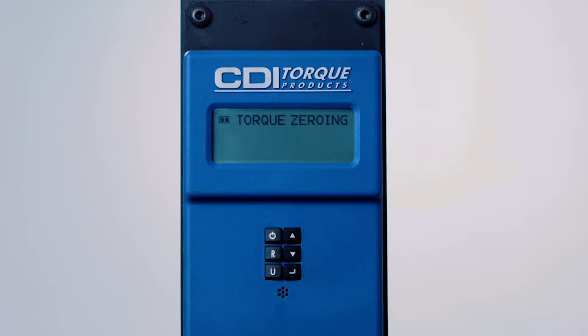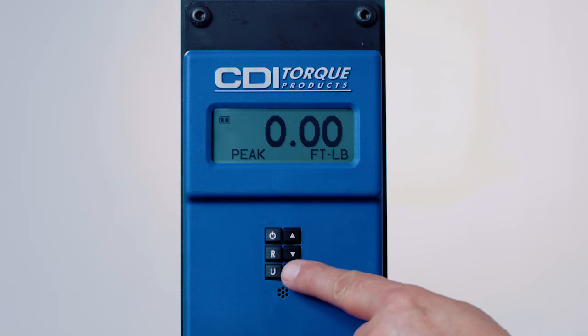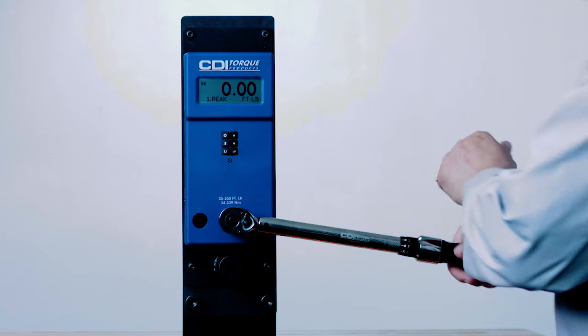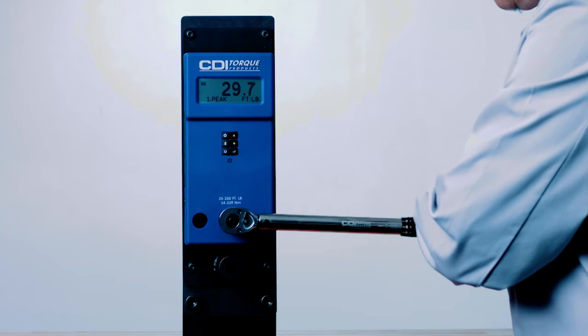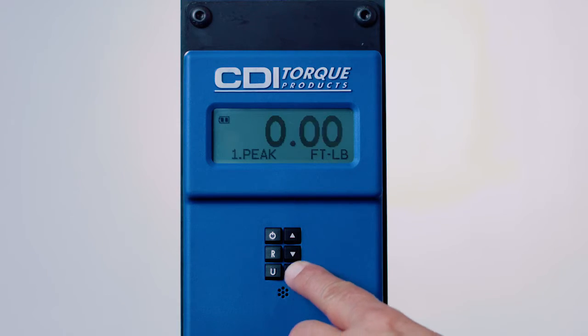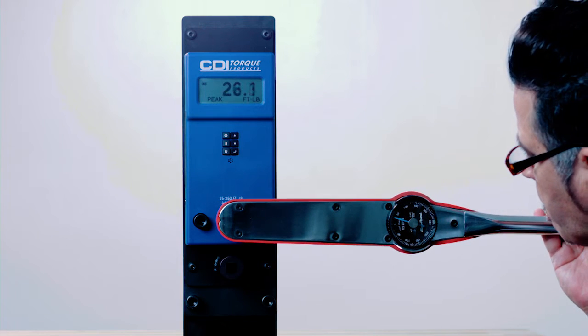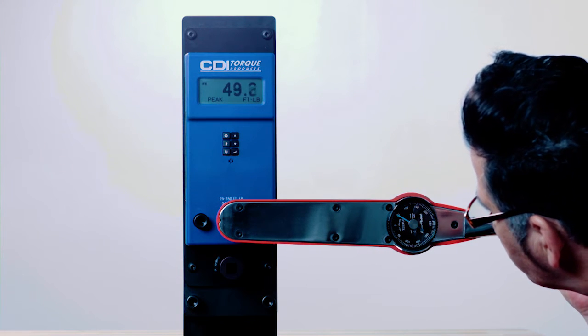Pressing the enter button allows you to select one of three modes. First peak, displayed on the checker as 1 peak, is used for checking mechanical click type torque wrenches. Peak mode is used for checking dial type torque wrenches. This mode is also useful for training in the proper use of a click type torque wrench. Track mode may also be used for dial type torque wrenches.